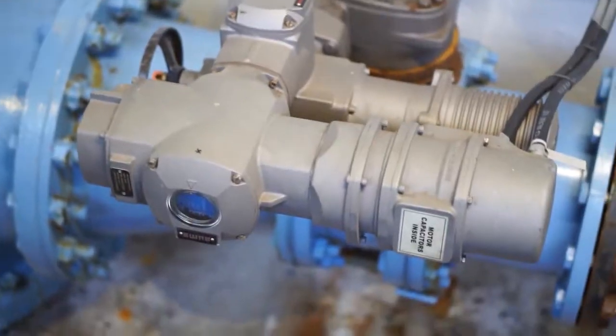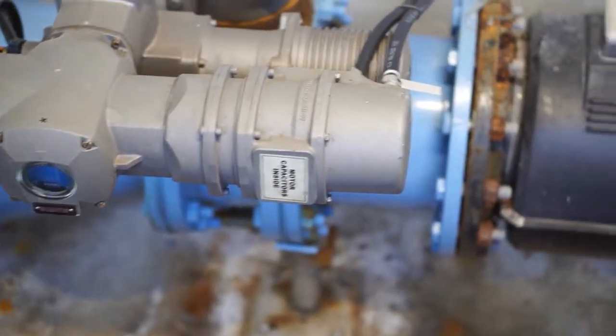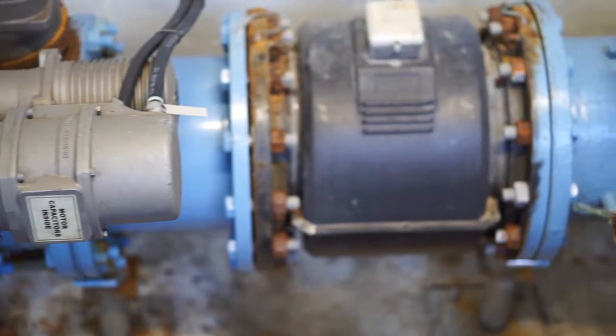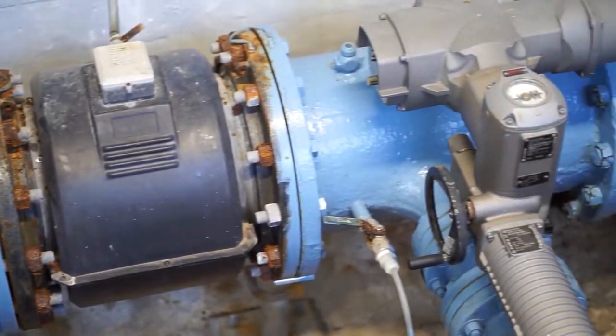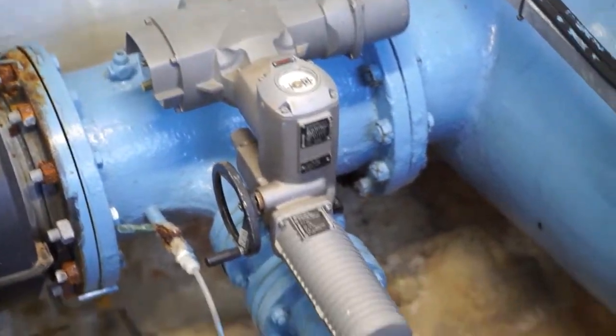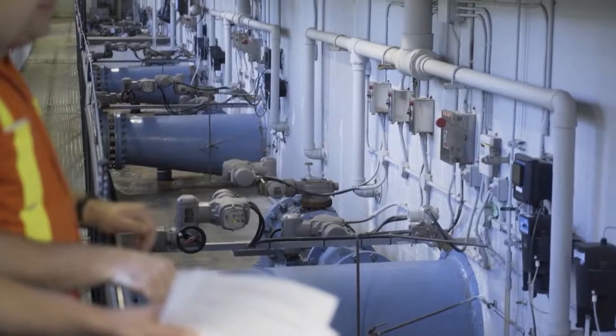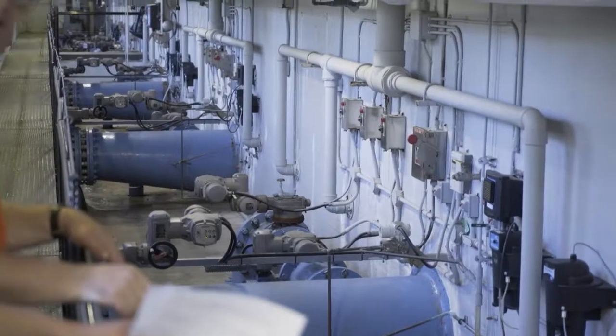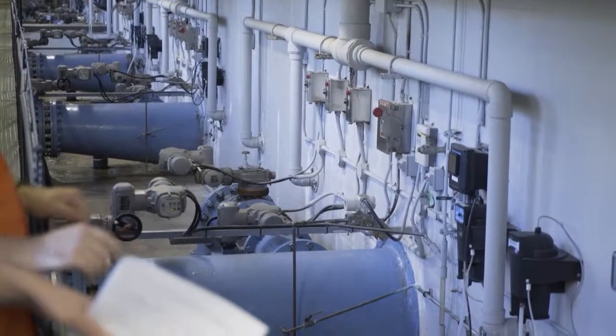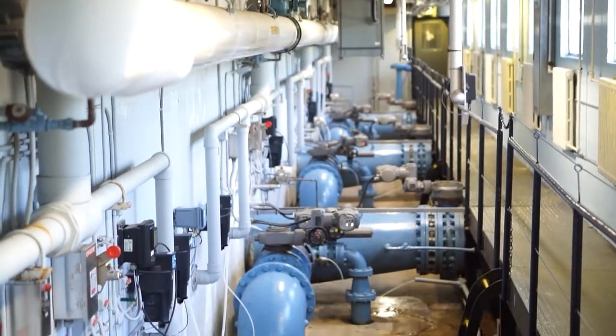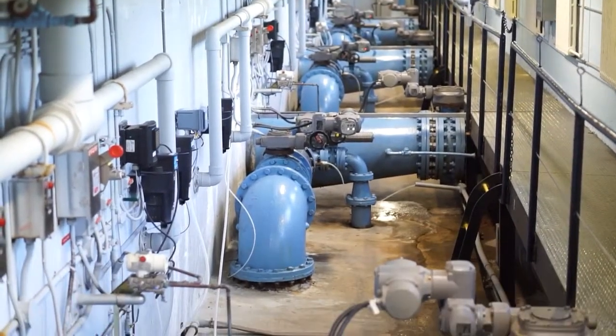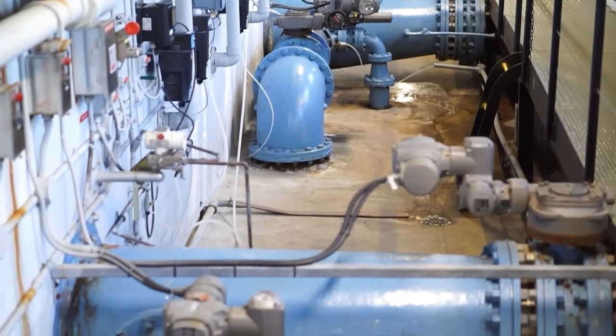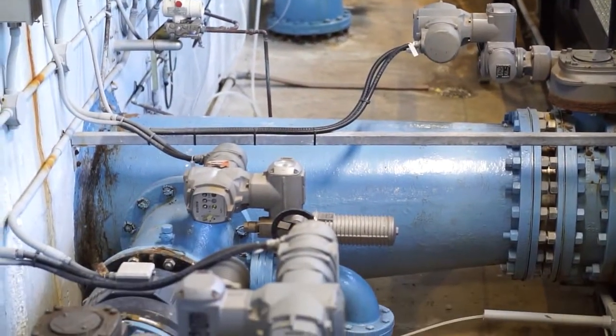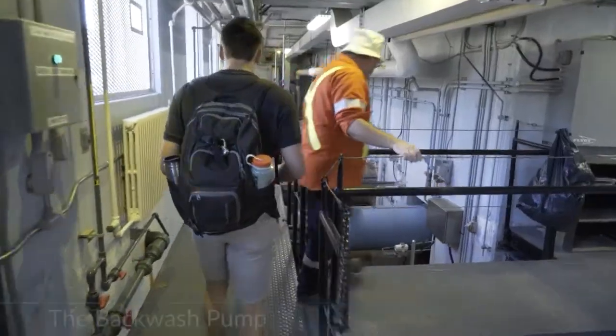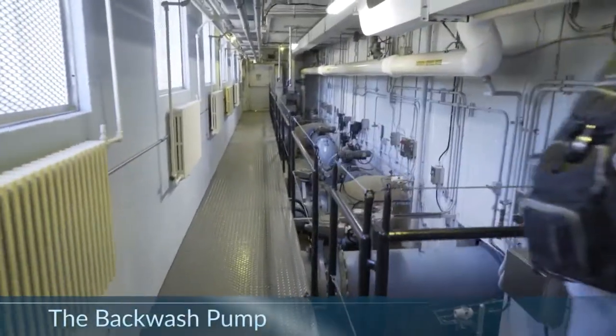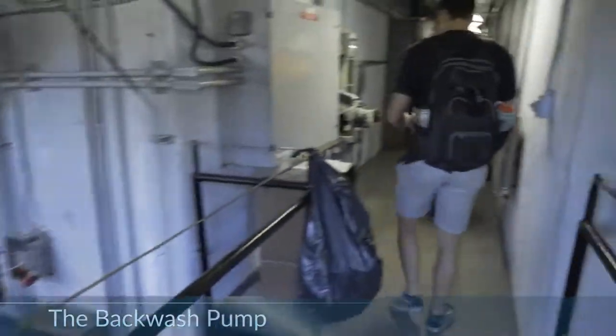Flow meter and flow control valves on these pipes control how much water passes through the filter, and also control the backwash that cleans the filters and filters the floc to waste. The backwash water is unchlorinated water from the clear well, which is pumped using a low-lift style pump, i.e. high capacity, low pressure, back through the filters.